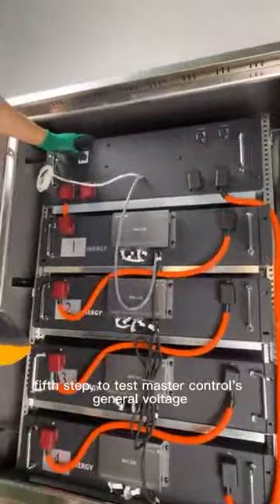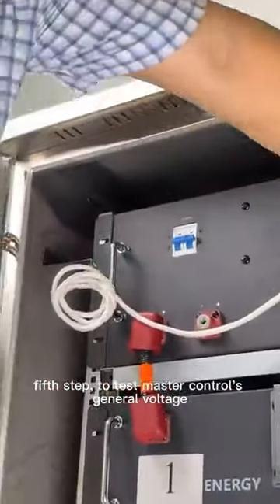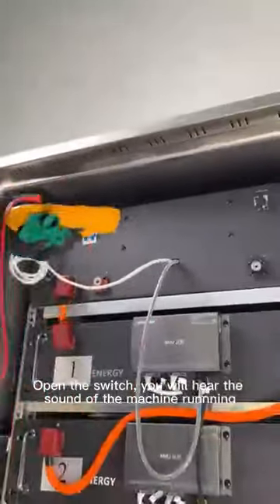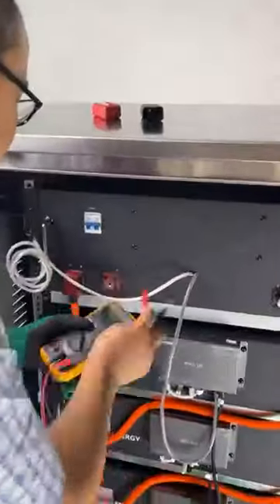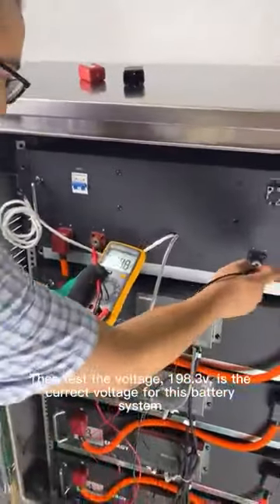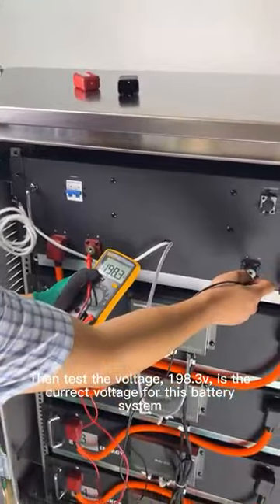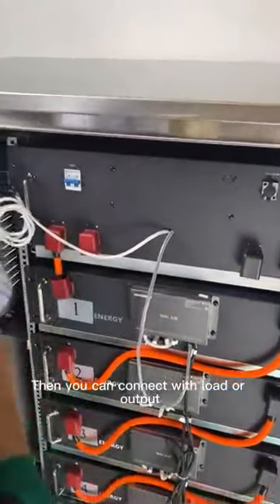Fifth step, test master controls general voltage. Open the switch, you will hear the sound of the machine running. Then test the voltage. 198.3 voltage is the correct voltage for this battery system. Then you can connect with load or output.